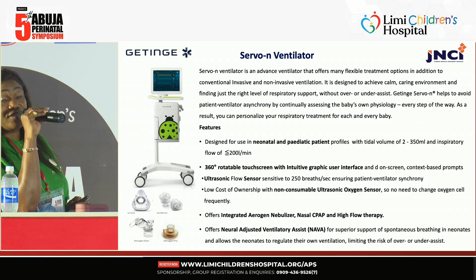So, still on the Servo N ventilator, it offers the option for the measure and display of electrical activity, like I mentioned. It is able to do high-frequency oscillatory ventilation, HFOV. This is a technology that is seen in no other ventilator at the moment. Other ventilators do high oscillations, they do oxygen delivery and high flow therapies, but this does high frequency oscillatory ventilation. And it gives you the option to monitor your CO2s. We also have one unique and distinct feature, which is the open lung tool.